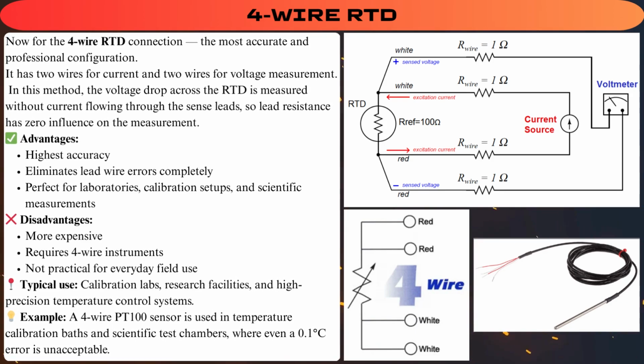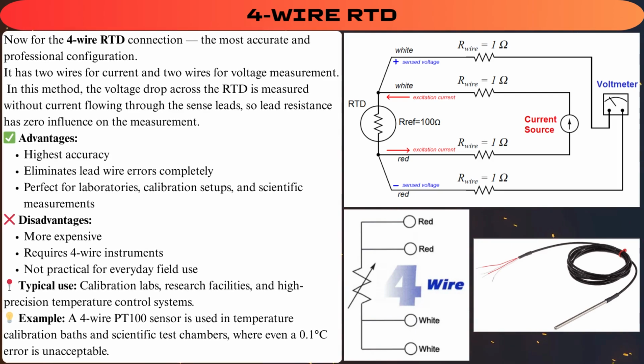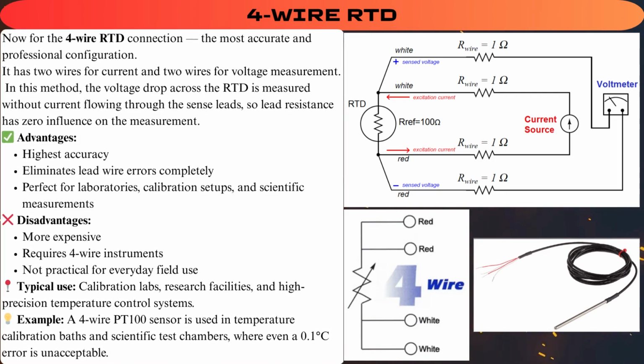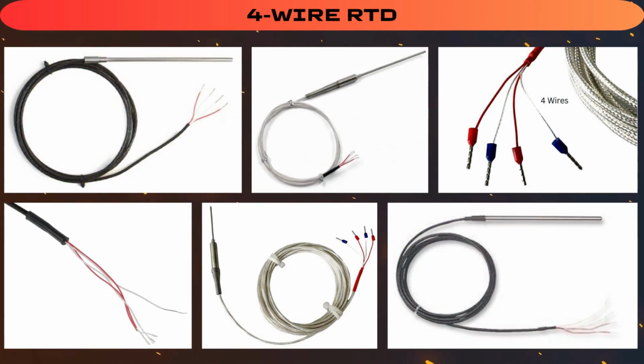Advantages: highest accuracy. Eliminates lead wire errors completely. Perfect for laboratories, calibration setups, and scientific measurements. Disadvantages: more expensive. Requires 4-wire instruments. Not practical for everyday field use. Typical use: calibration labs, research facilities, and high-precision temperature control systems. Example: A 4-wire PT100 sensor is used in temperature calibration baths and scientific test chambers where even a 0.1 degrees Celsius error is unacceptable.